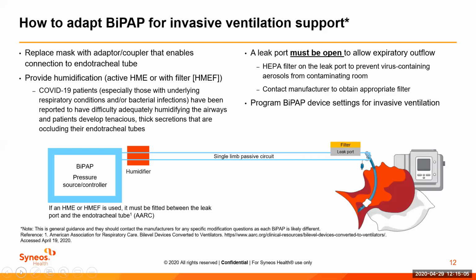Yes, let's look over to the left side of the screen. We see the BiPAP pressure source controller. What we have to first recognize is that when we're considering BiPAP, it's bi-level pressure. That means it has an inspiratory pressure and an expiratory pressure. Now we can set this machine for volume, for pressure, for a certain amount of inspiratory time. We're essentially setting this BiPAP device the same way we do these advanced mechanical ventilators that we use in the critical care environment. Each breath delivered to a patient, whether they be actively breathing or passively breathing, is determined by three things: pressure, volume, and time.